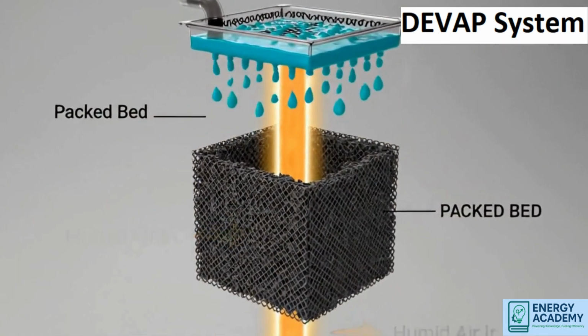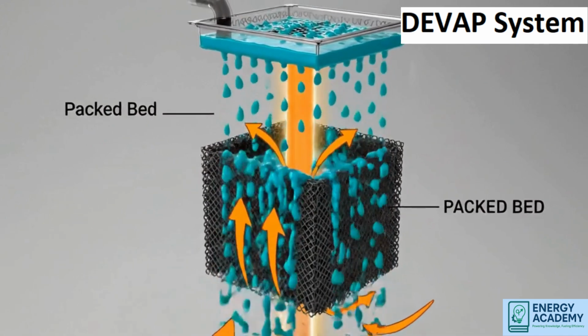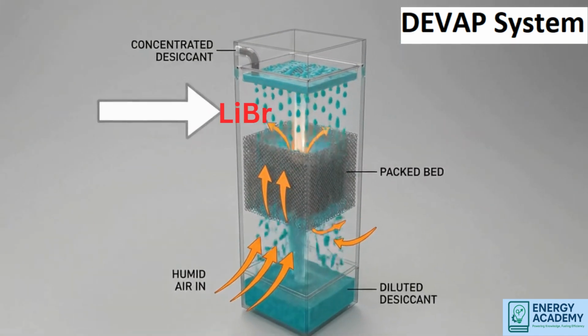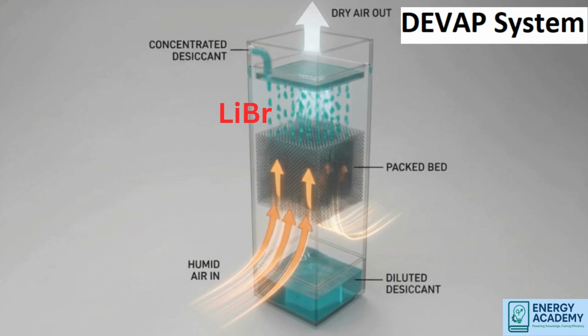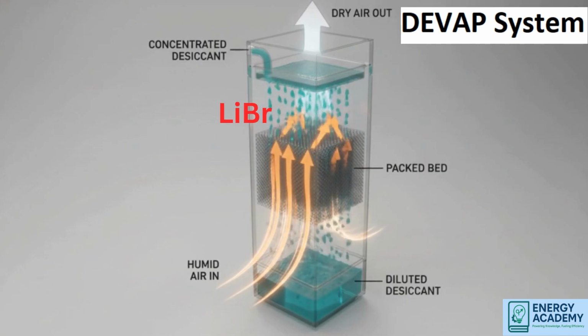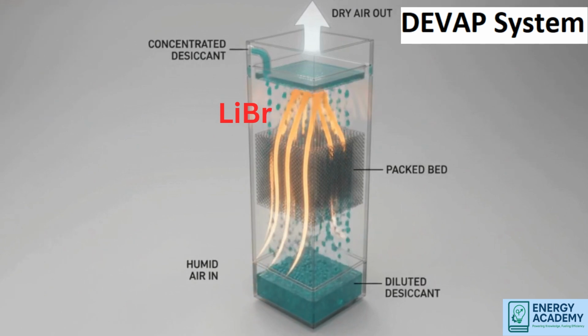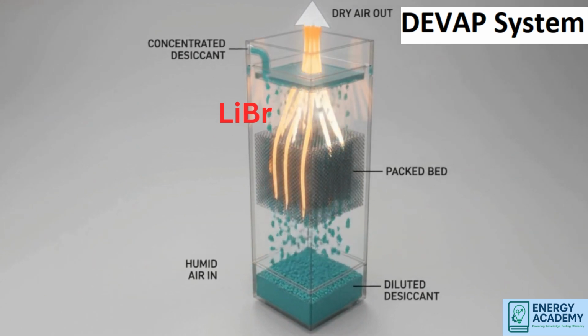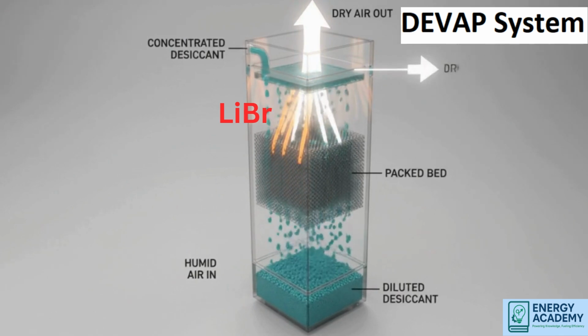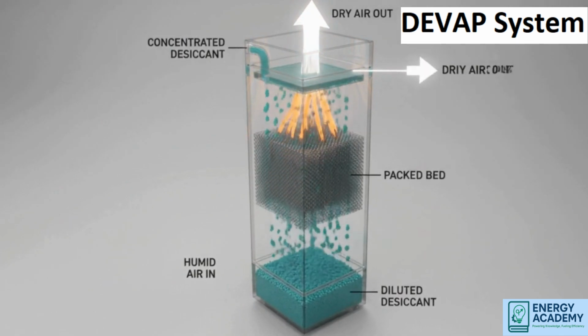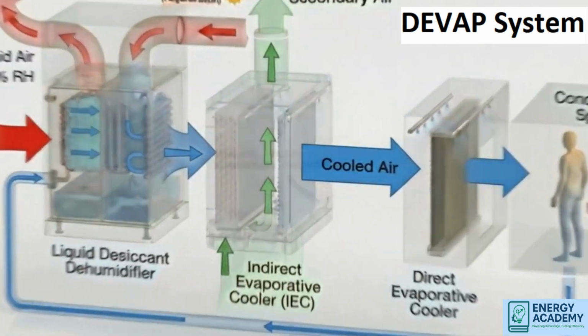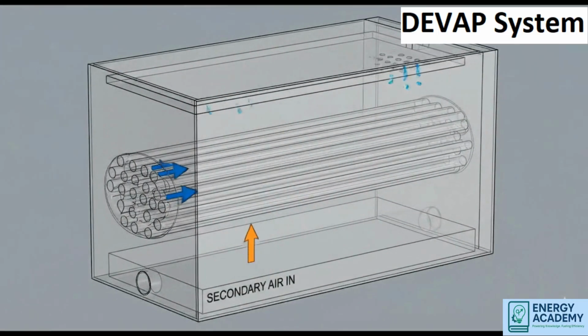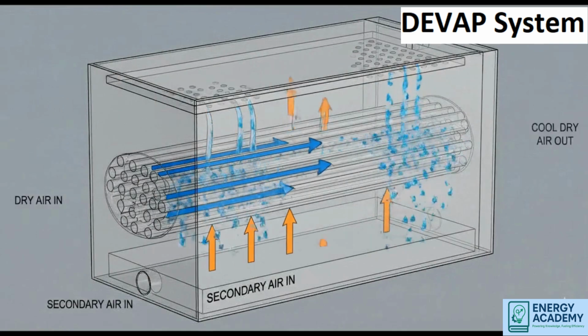First, hot and humid outdoor air enters the DEVAP system, carrying both sensible and latent heat. Then, a liquid desiccant absorbs moisture directly from the air. This removes latent heat chemically, without compressors, eliminating nearly 70% of cooling energy demand. After dehumidification, the air becomes dry, ideal for efficient evaporative cooling.